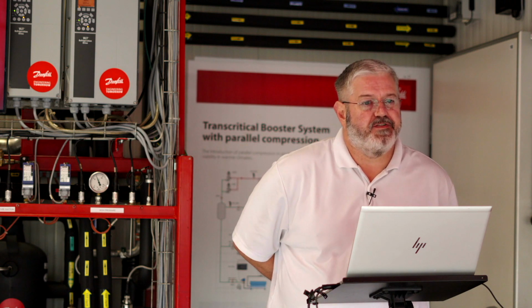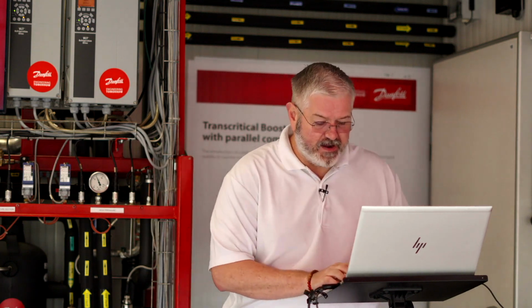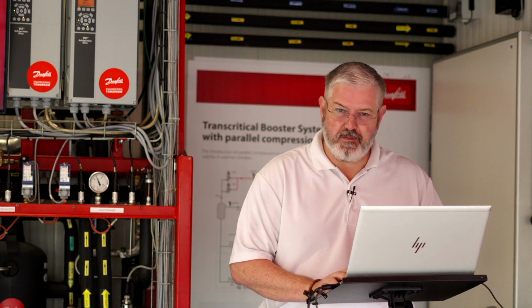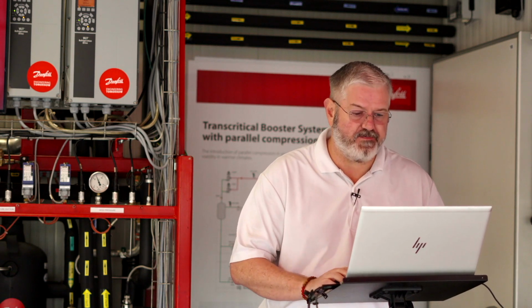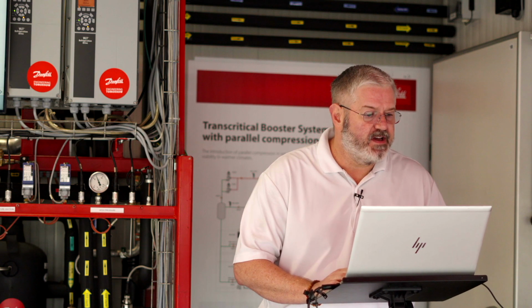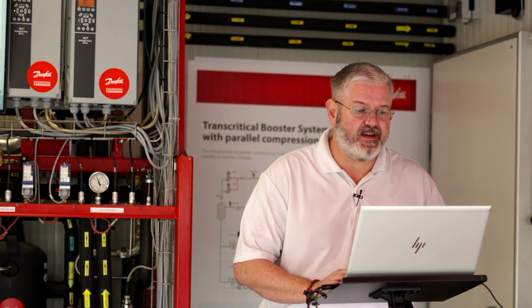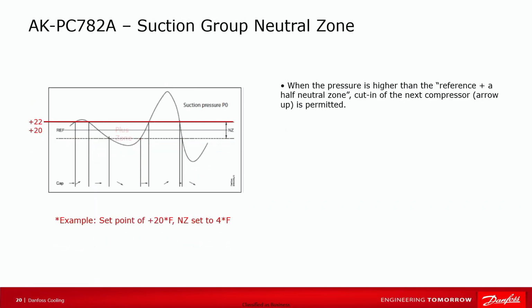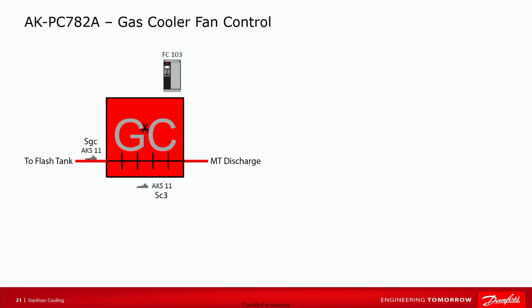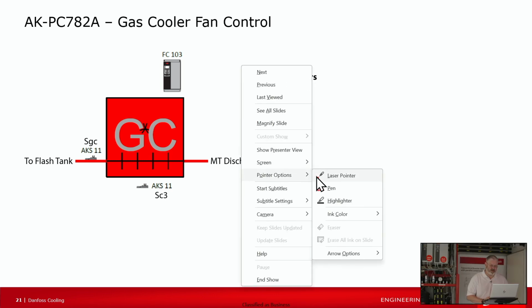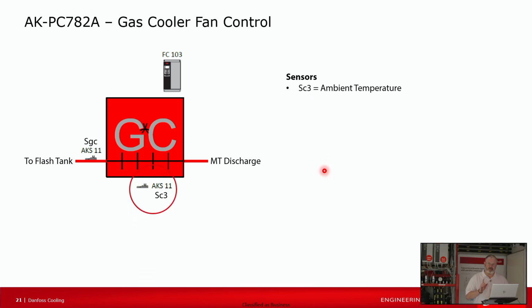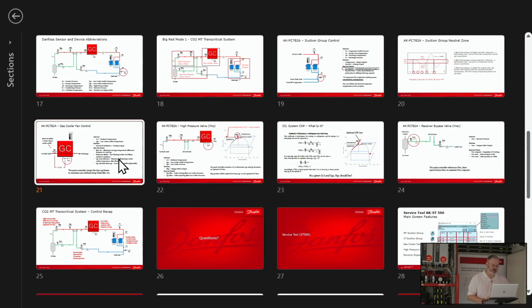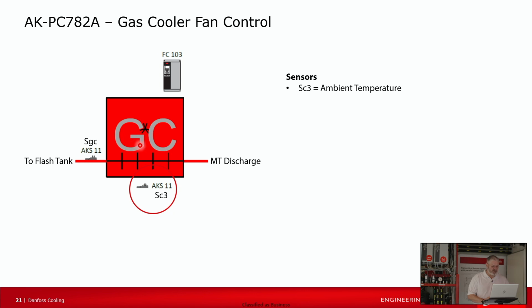Can the fans and high pressure valve fight each other? That's a great question, and the answer is actually no. If you'll remember back, let me see if I can bring this up. My apologies, I'm going to jump slides, so the presentation, if it's on your screen, is going to look awkward for a moment. So if we go back to our fans. Okay, condenser fan control. All we're doing on condenser fan control is controlling between, give me one moment to jump back in gear here. So the question was, can the high pressure valve and the condenser fans fight each other? All right, PowerPoint is smarter than me for the moment.